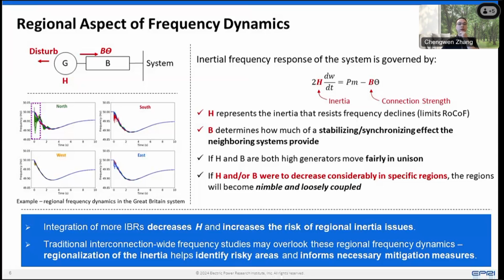If both H and B are at a very high level, which can be true for most parts in traditional power systems, you can expect this generator to move pretty coherently with the rest of the system when there is a frequency disturbance. But if inertia decreases or the connection strength is insufficient, you can expect this region or generator to behave differently, or even more drastically different, from the rest of the system.